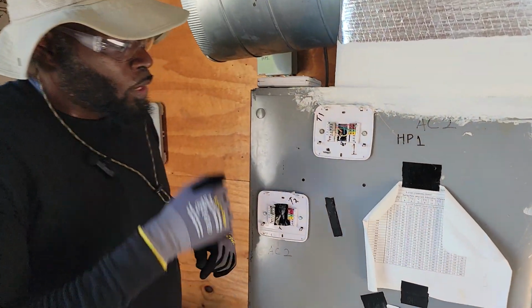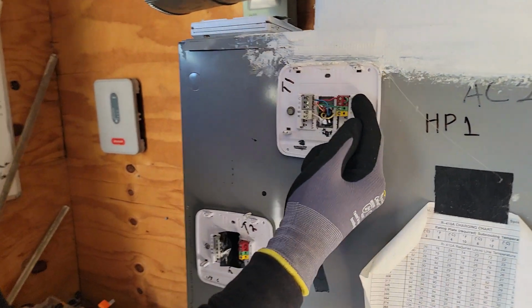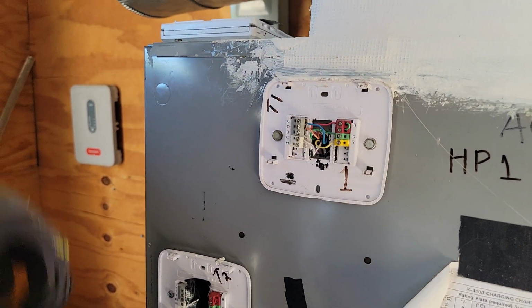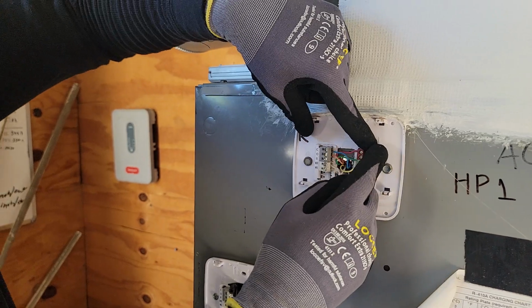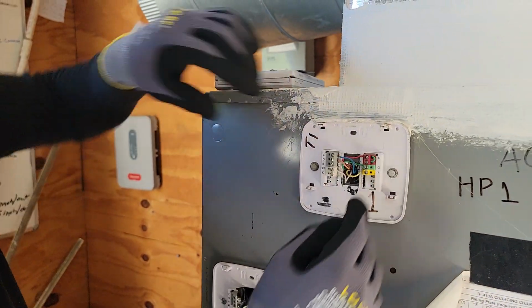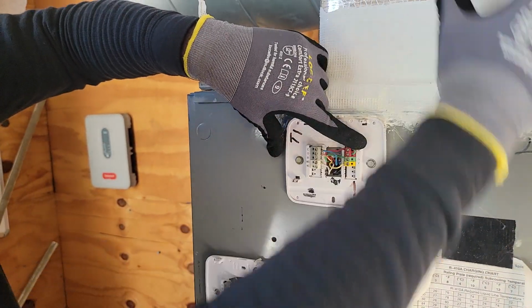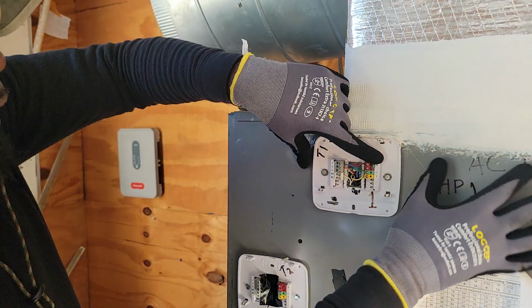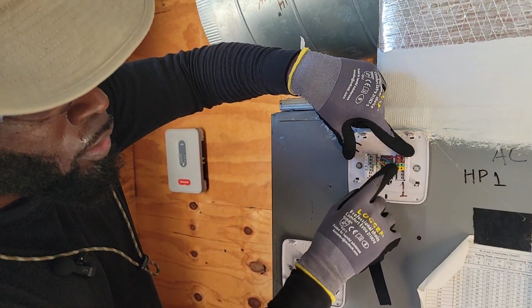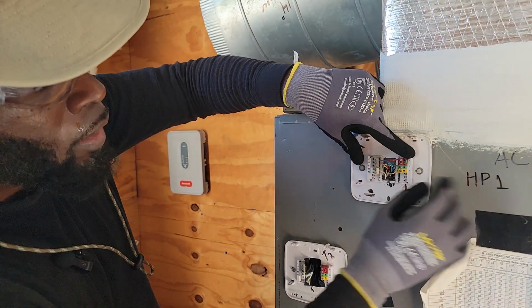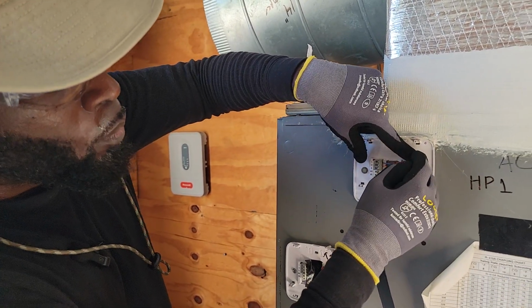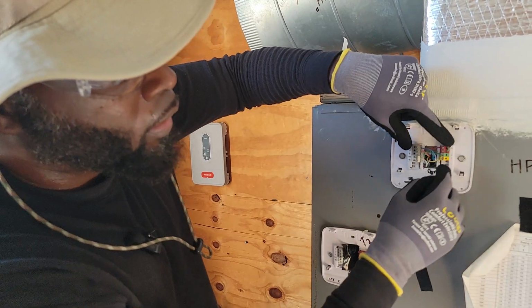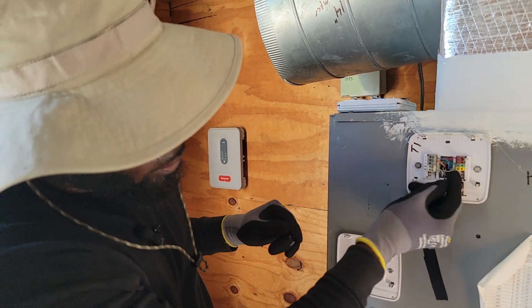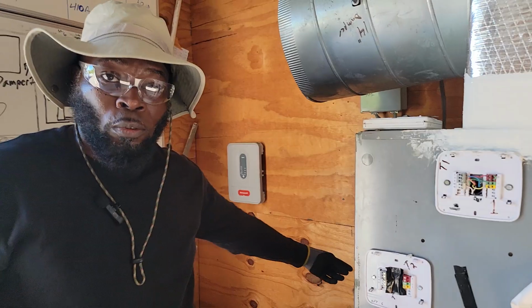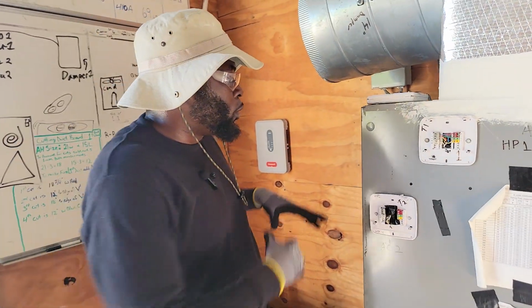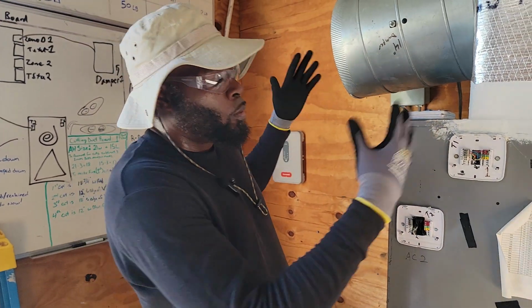So when we come to the thermostat, we got our R, G, and Y. R is our common 24 voltage. Nothing works without the R. In order for it to turn on your air handler, your air blower motor inside of the air handler, R has to connect with G. G is the blower motor inside of here. So R connects to G, R connects to Y, which is the yellow wire right here. It goes out to your condenser unit, contactor, and it turns the condenser unit on. And now we get cooled air.